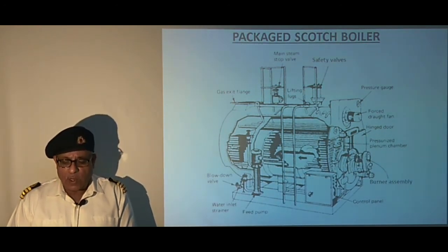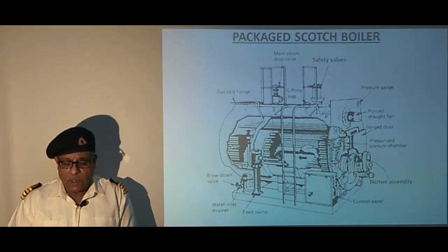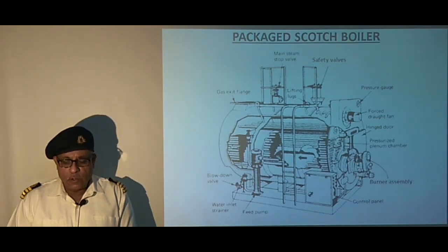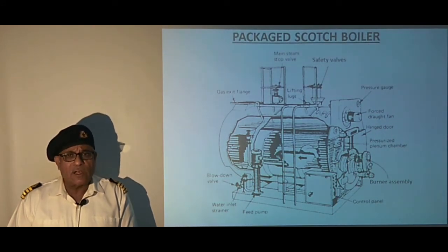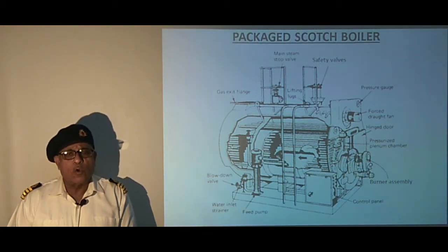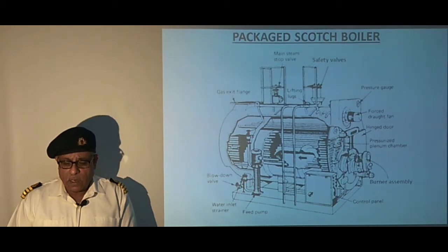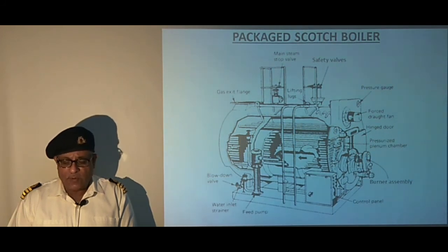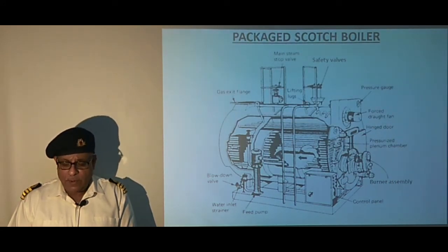To relieve internal pressure, the boiler is equipped with an improved high-lift safety valve with an easing gear arrangement. The blow down valve used to be a non-return type to prevent entry of sea water, as earlier boilers were installed below the load water line. Nowadays boilers are installed above the water line, and the blow down valve is connected with an internal pipe to completely empty out the boiler when required.